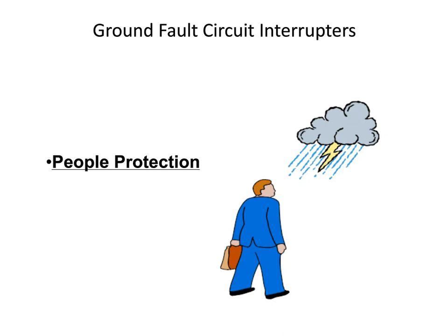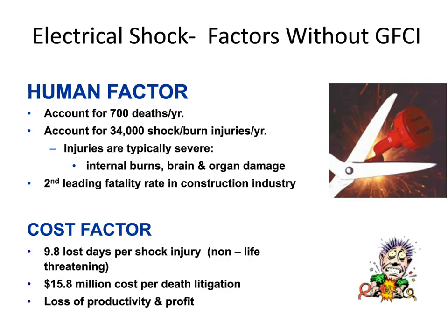Now, the first thing I want to point out is when we're talking about ground fault products from Hubbell, we're talking about type A ground fault protection. That is ground fault products that trip within the 4 to 6 milliamp range that are designed for people protection. There is also ground fault products that exist that are designed for equipment protection. That is type B ground faults. There's product that trips between 5 and 30 milliamps. There's 30 milliamp and higher.